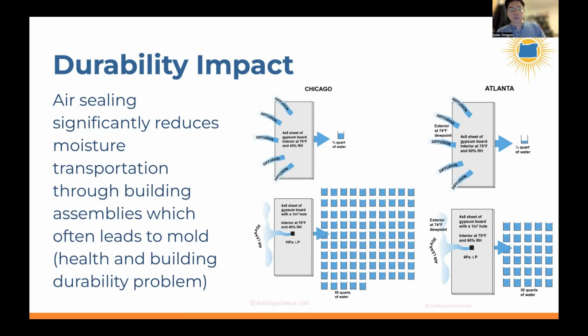Here's some work that Joe Lstiburek at Building Science Corporation did to look at how much water in the form of moisture can be transported through a 1 inch square hole—a very small hole in the grand scheme of things. He did analysis and testing and found that in the Chicago climate zone, a 1 inch square hole can transport 95 quarts of water over the course of a season. That's a ton of water, way more than is needed to cause a mold problem inside a building assembly, which leads to building durability problems and health problems. So getting air leakage down to 0.6 or 1 air change per hour contributes a lot to building durability.